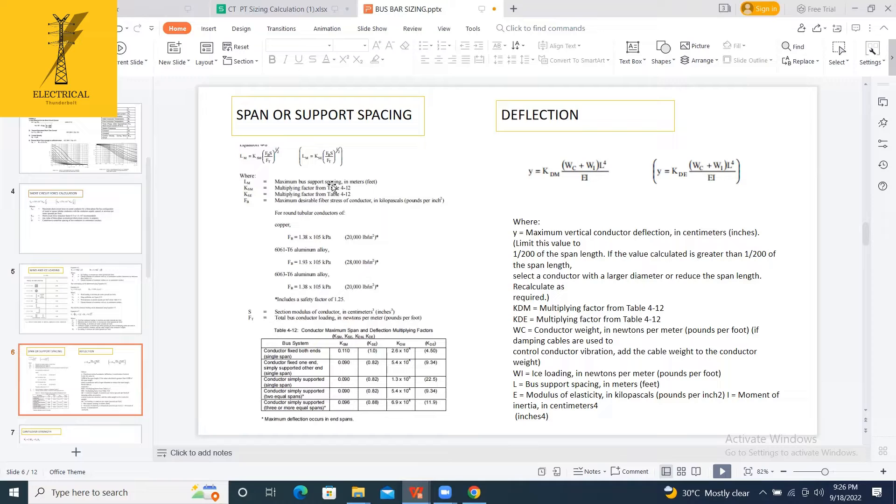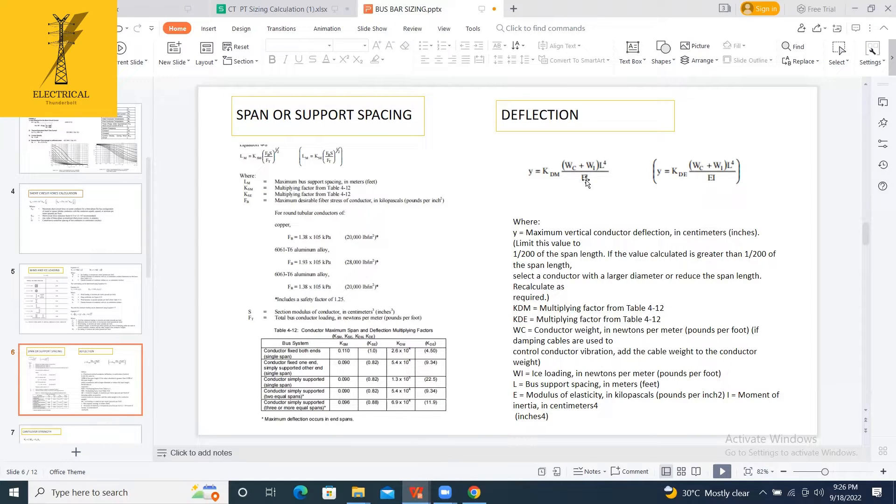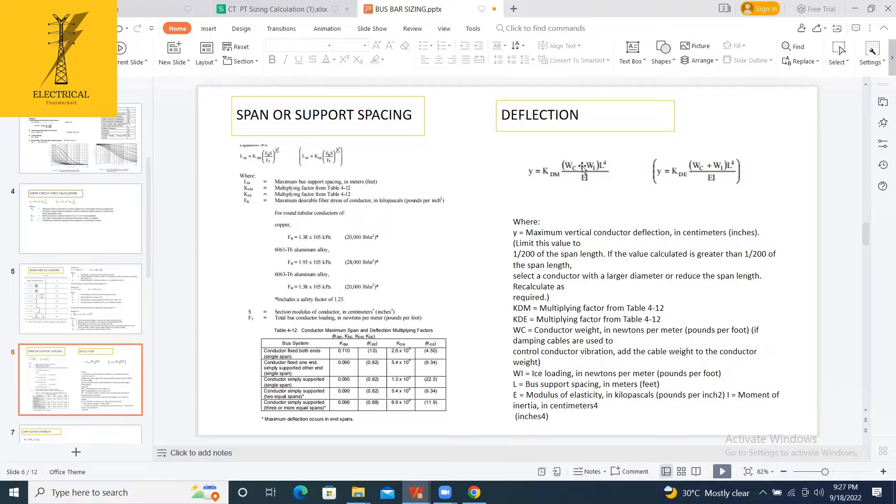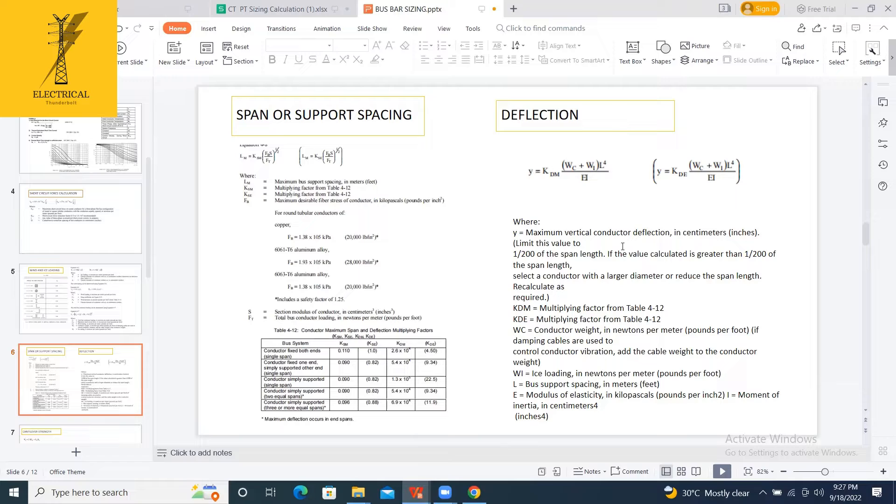After that span, I am calculating what is the maximum vertical conductor deflection. We are having support spacings, right? So what is the deflection for that? That will again depend upon your loadings. What loadings? Deflection from the top. Obviously, here only the wind loading and the conductor weight will come. The short-circuit forces or wind forces will not be there. It is directly from the top.